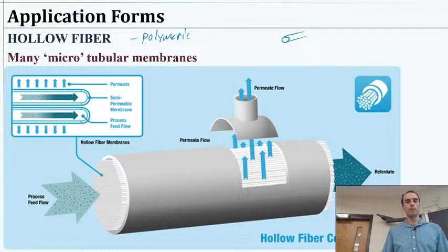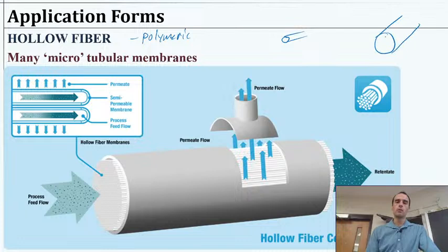It's operating just like the tubular membranes otherwise. And one thing to note here, and we'll do a problem on this, if you have any sort of a tubular membrane, whether it's large or it's these hollow fibers, you're going to have some geometry at play, because your surface area for the filter, and the surface area is going to be very important, it can either be dictated by that inner diameter if you are operating from inside out, or it could be the outer diameter if you're going from outside in terms of the direction of filtration. So we have an outer or an inner diameter.